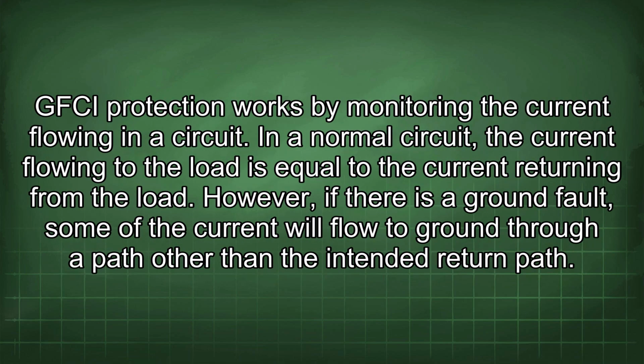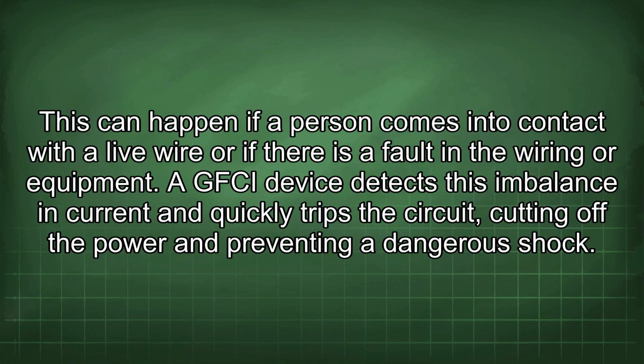GFCI protection works by monitoring the current flowing in a circuit. In a normal circuit, the current flowing to the load is equal to the current returning from the load. However, if there is a ground fault, some of the current will flow to ground through a path other than the intended return path. This can happen if a person comes into contact with a live wire or if there is a fault in the wiring or equipment.